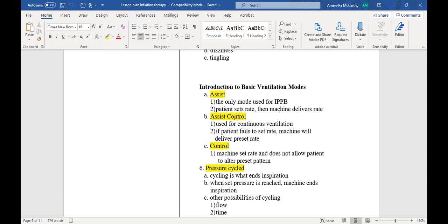So soon as you suck in a little bit, the positive pressure is going to fill you up. You don't have to keep pulling, right? You don't have to keep sucking on it. Once you trigger the breath, all you got to do is let the machine hyperinflate you. That's when we're doing positive pressure, right? When we're doing positive pressure, all you have to do is trigger it, and it will fill your lungs up. It's going to pop them lungs open for you, all right? And it's going to do that until it reaches the pressure that I have set for it.